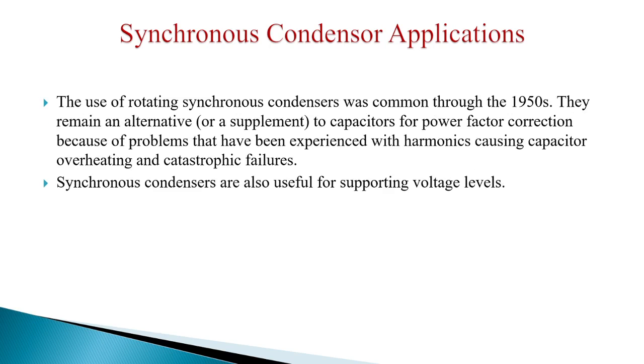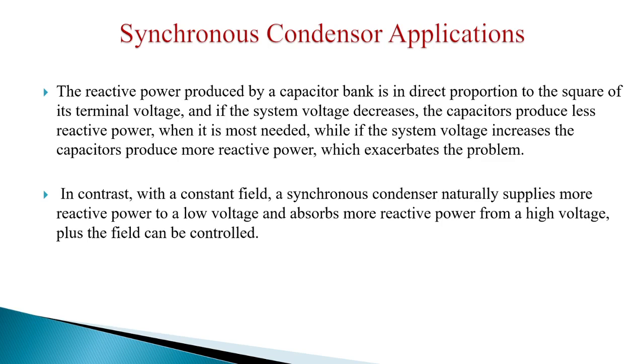The use of rotating synchronous condensers was common in the 1950s. They remain as a supplement to capacitors for power factor correction because of problems that have been experienced with harmonics, causing capacitor overheating and catastrophic failures. Synchronous condensers are useful for supporting voltage levels.